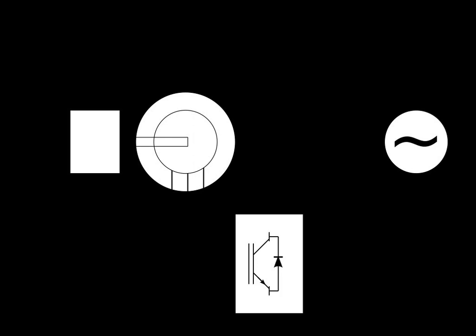In order to prevent high rotor voltages, and high currents resulting from these voltages, from destroying the IGBTs and diodes of the converter, a protection circuit called a crowbar is used. The crowbar will short-circuit the rotor windings through a small resistance when excessive currents or voltages are detected. In order to be able to continue the operation as quickly as possible, an active crowbar has to be used.